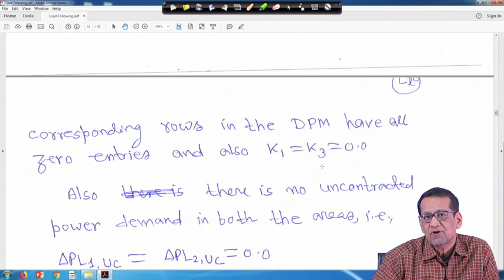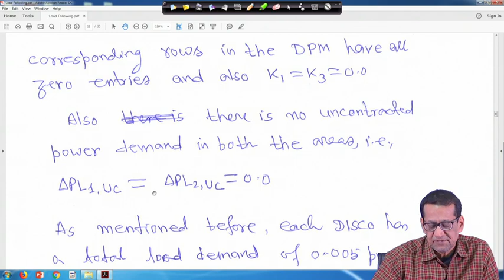It may be noted that since unit 1 and unit 3 are not in load following, the corresponding rows in the DPM have all zero entries, and also K1 and K3 are 0, because they are not taking part in load following. The load following controller gain for unit 1 was K1 and for unit 3 was K3, as shown in the block diagram. So K1 equals K3 equals 0. Also we assume there is no uncontracted power demand in both areas, so delta PL1 UC and delta PL2 UC are equal to 0.